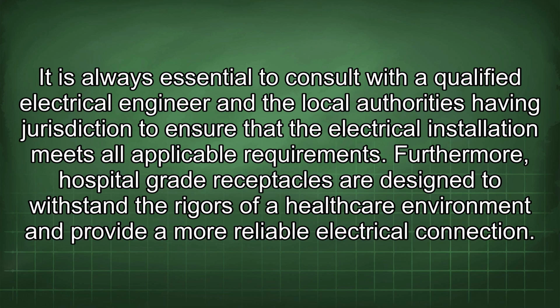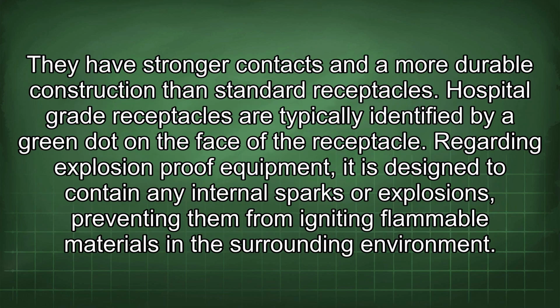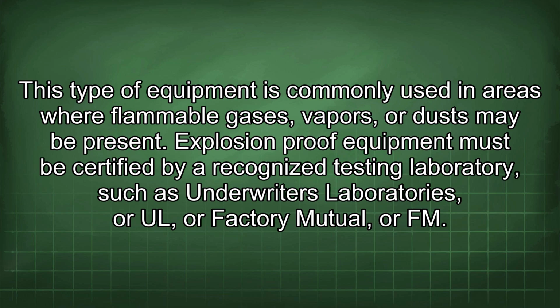Furthermore, hospital-grade receptacles are designed to withstand the rigors of a healthcare environment and provide a more reliable electrical connection. They have stronger contacts and a more durable construction than standard receptacles. Hospital-grade receptacles are typically identified by a green dot on the face of the receptacle. Regarding explosion-proof equipment, it is designed to contain any internal sparks or explosions, preventing them from igniting flammable materials in the surrounding environment. This type of equipment is commonly used in areas where flammable gases, vapors, or dust may be present. Explosion-proof equipment must be certified by a recognized testing laboratory, such as Underwriters Laboratories, or Factory Mutual, or FM.